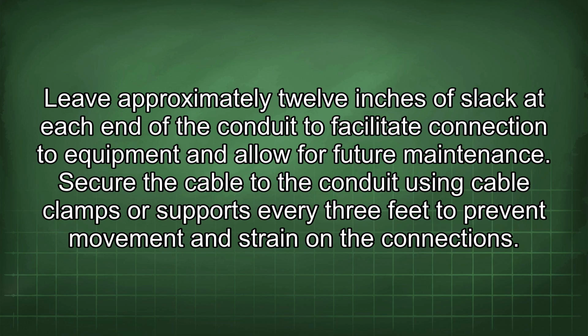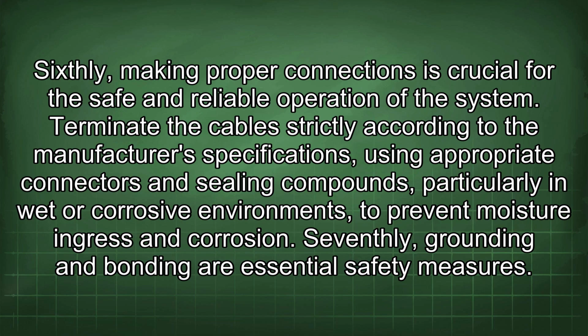Secure the cable to the conduit using cable clamps or supports every 3 feet to prevent movement and strain on the connections. Sixthly, making proper connections is crucial for the safe and reliable operation of the system. Terminate the cable strictly according to the manufacturer's specifications, using appropriate connectors and sealing compounds, particularly in wet or corrosive environments, to prevent moisture ingress and corrosion.